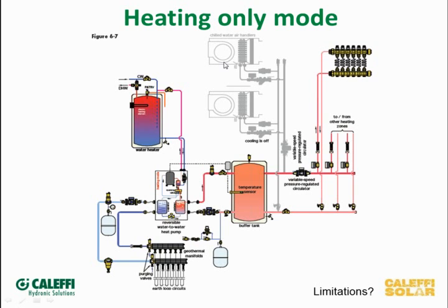It wouldn't be possible to switch quickly from heating to cooling, because now you've got your buffer tank loaded up, in this case with heating. Let's say the sun comes up by noon, and people are saying, I'm getting too hot in here, I need my cooling back on. Well, it's not going to be possible to switch gears quickly there. So this would be a fairly limited application system once again, but there are applications where this system does fit.